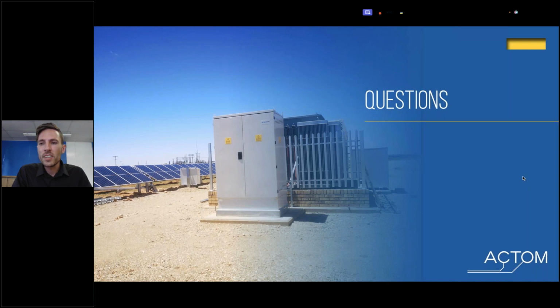On the bigger transformers, it makes sense because you're paying a couple of million. Most already have a DGA device paid for as part of manufacturing, so getting the data is a minimal upfront cost or a monthly SLA cost, not rocket science to work out. On smaller transformers, it wouldn't be advisable to put a full DGA on it, more likely a 2 gas DGA. We'd recommend it from about 40 MVA upwards, since most of those transformers already have a DGA as part of the installation. But we can give a solution on any size transformer.